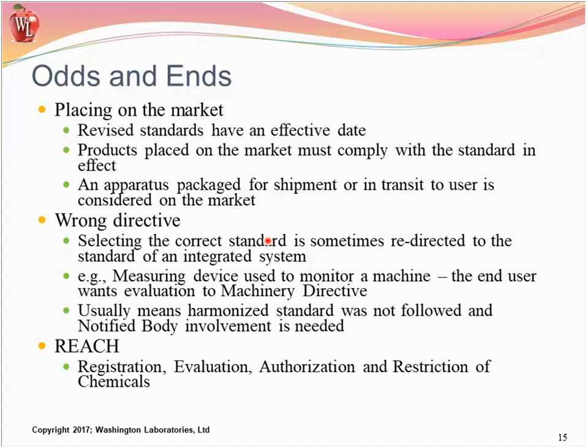Sometimes the wrong directive is applied. An incorrect standard is sometimes redirected to the standard of an integrated system. For instance, I may have a piece of information technology equipment that I want to use in a measurement system. That laptop computer or whatever may need to comply not with the IT equipment standard 55024, but with 61326, because it's integral to the measurement system.